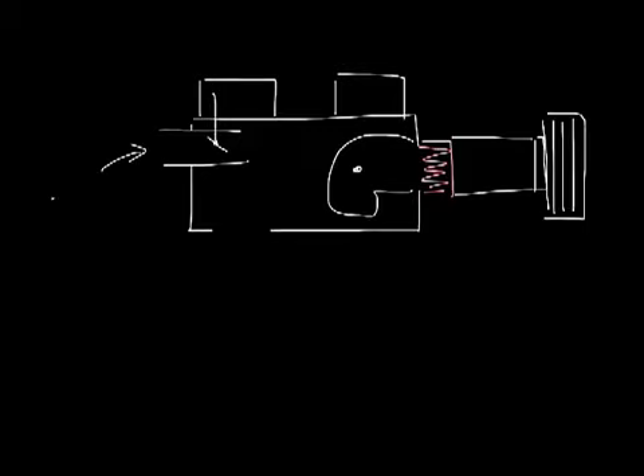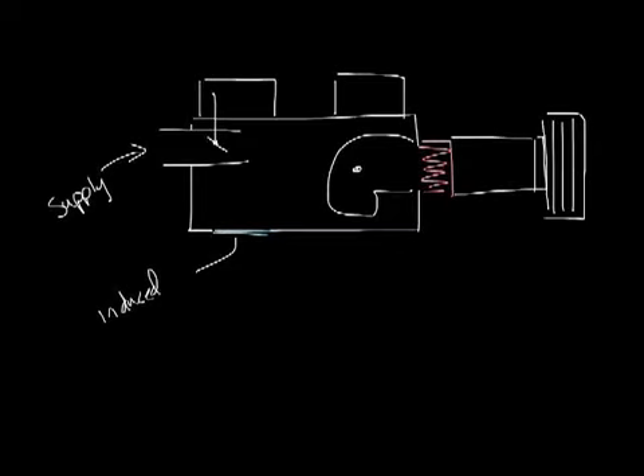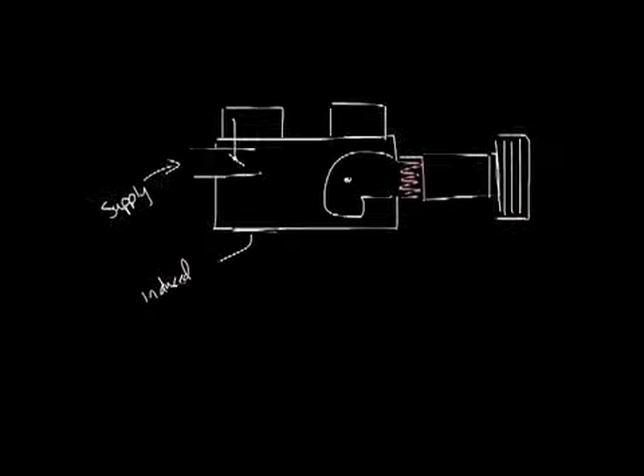Because the supply inlet and the induced air inlet were in the same plenum space, we were often asked to cap off the induced air inlet unless the engineer wanted to duct it to the return air. Since we were often capping off the induced air inlet, it just made sense to pull the air from the pressurized floor through the fan and then duct it into the space. Let's move this out of the way a little bit.